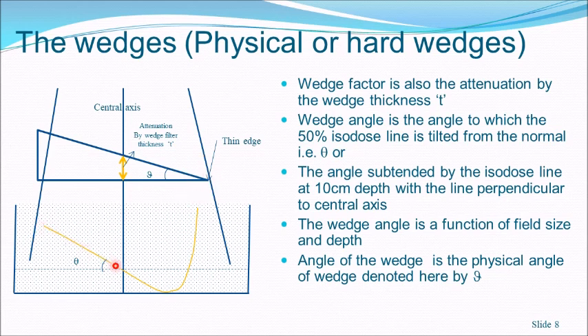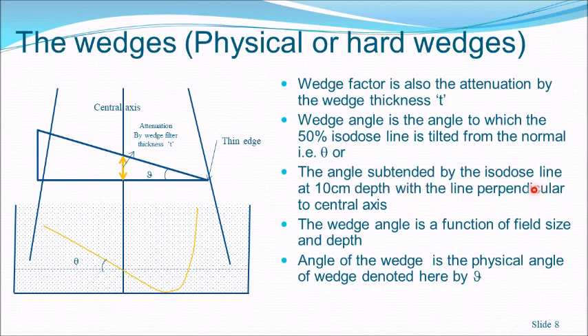Thus the isodose line is tilted to an angle. Physical wedges are normally provided in four common angles: 15, 30, 45, and 60 degrees. The wedge angle is the angle to which the isodose line is tilted from the normal. This tilt varies with depth, so the question is at what depth to measure the wedge angle. Older definition used the tilt of the 50% isodose line; currently, the wedge angle is defined as the angle subtended by the isodose line at 10 cm depth with the line perpendicular to the central axis.